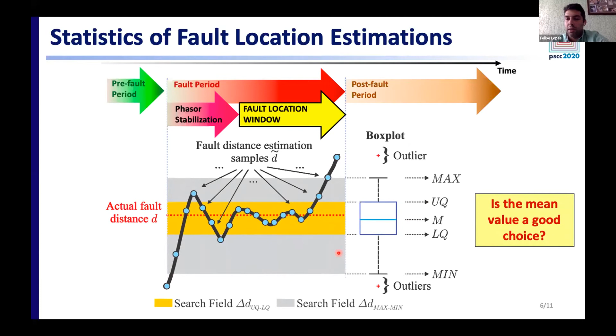To do so, an RTDS was used to simulate different fault cases in the same test system, from which an actual DFR was fed by voltage and current signals estimating phasors, which were then externally processed by a computer program responsible for calculating the box plot representation of the fault distance estimations obtained by means of 4 methodologies, among which we analyzed 1 single-ended method and 3 double-ended methods.